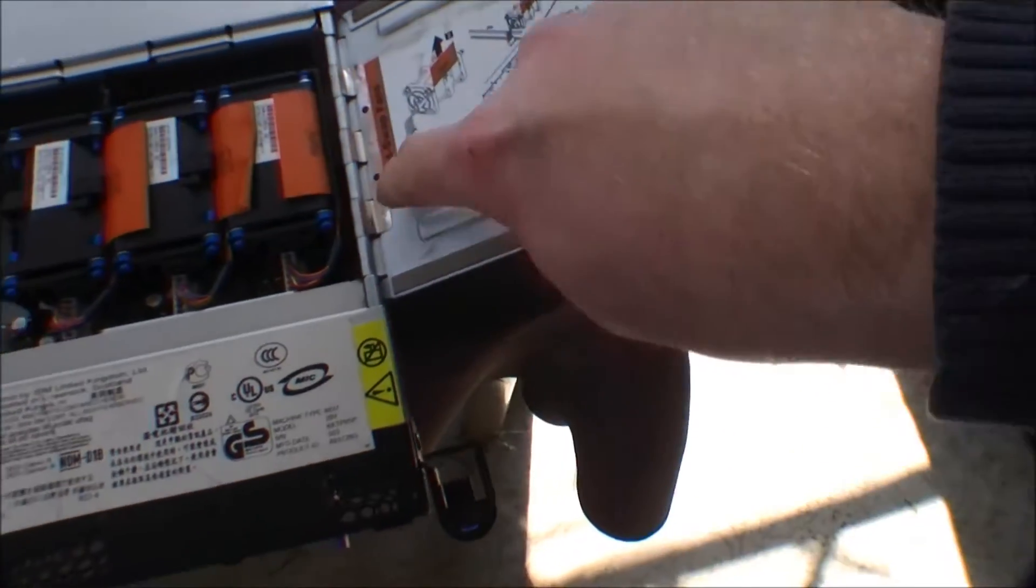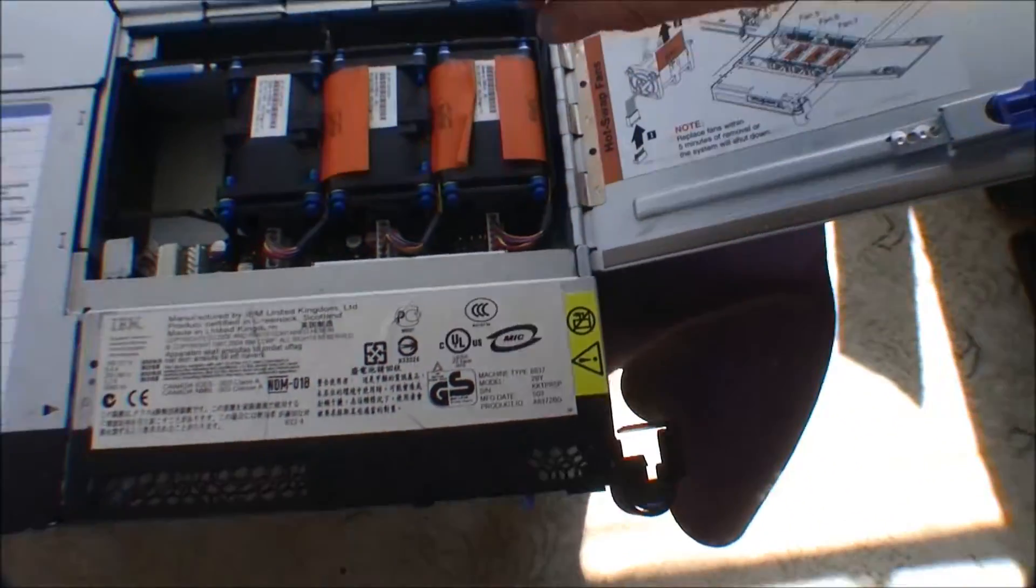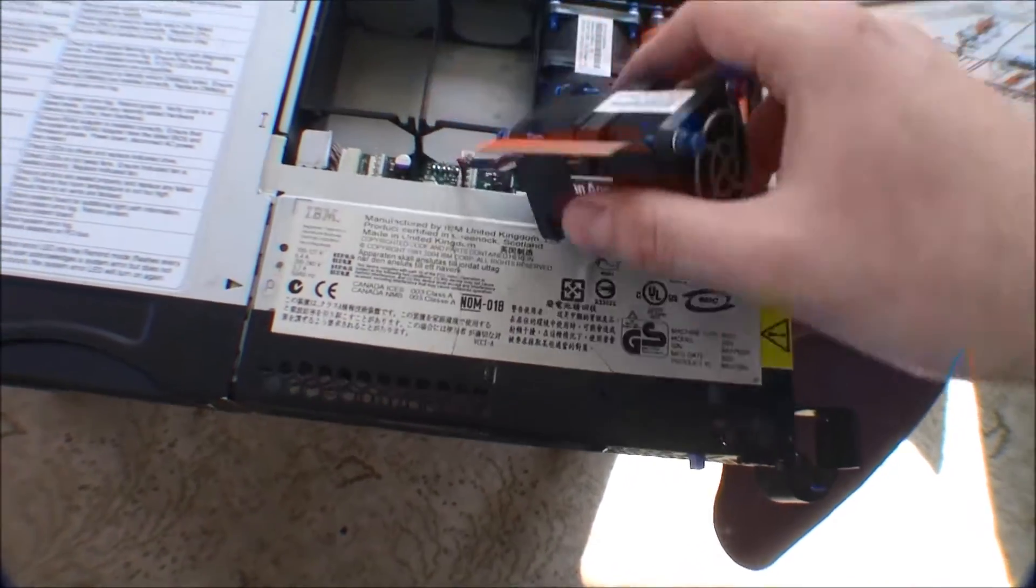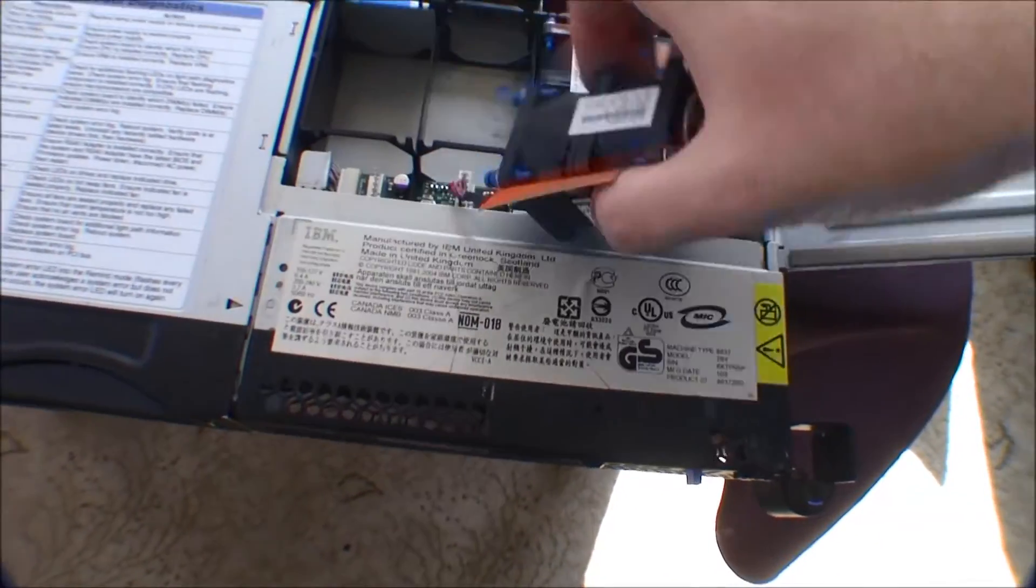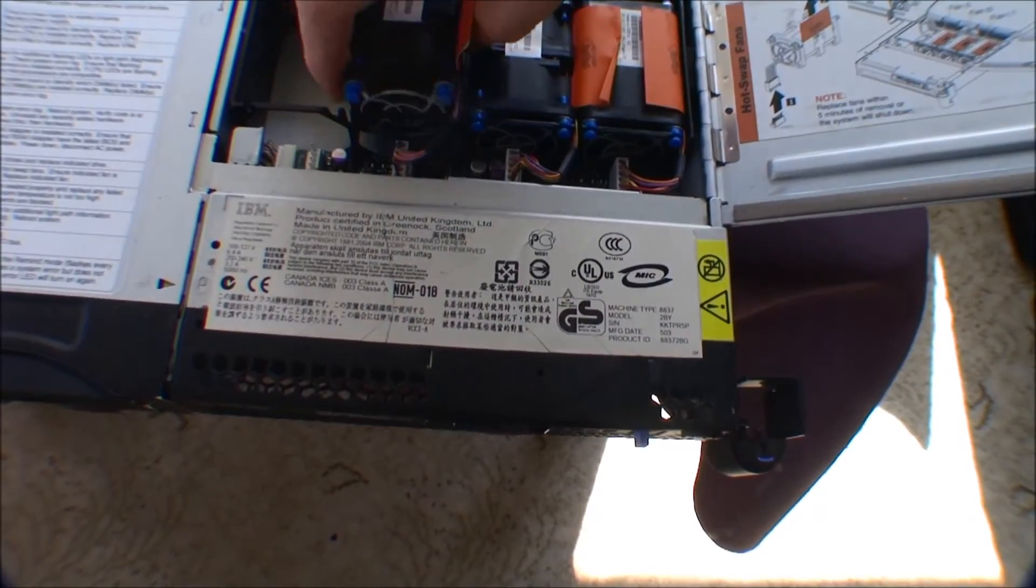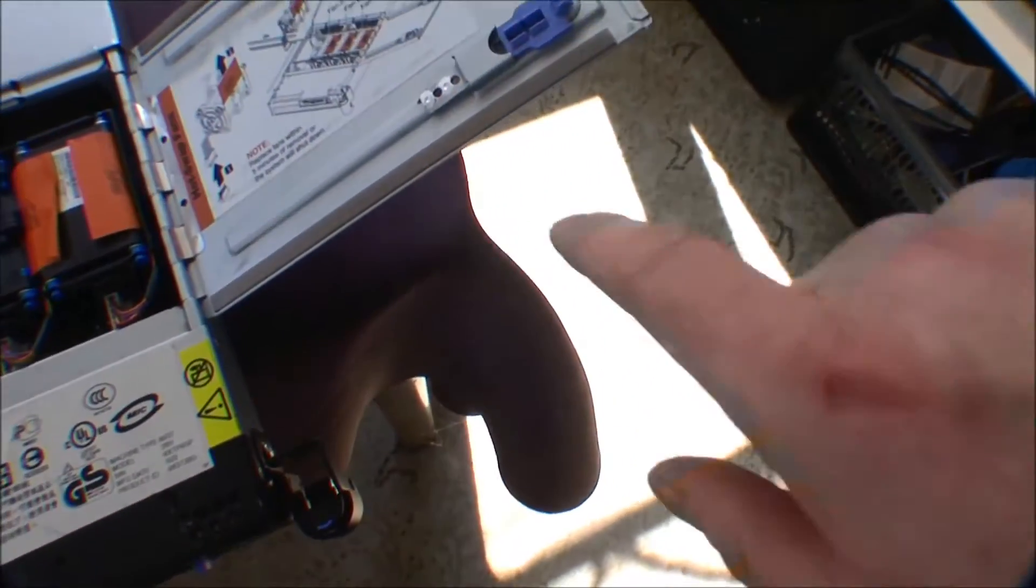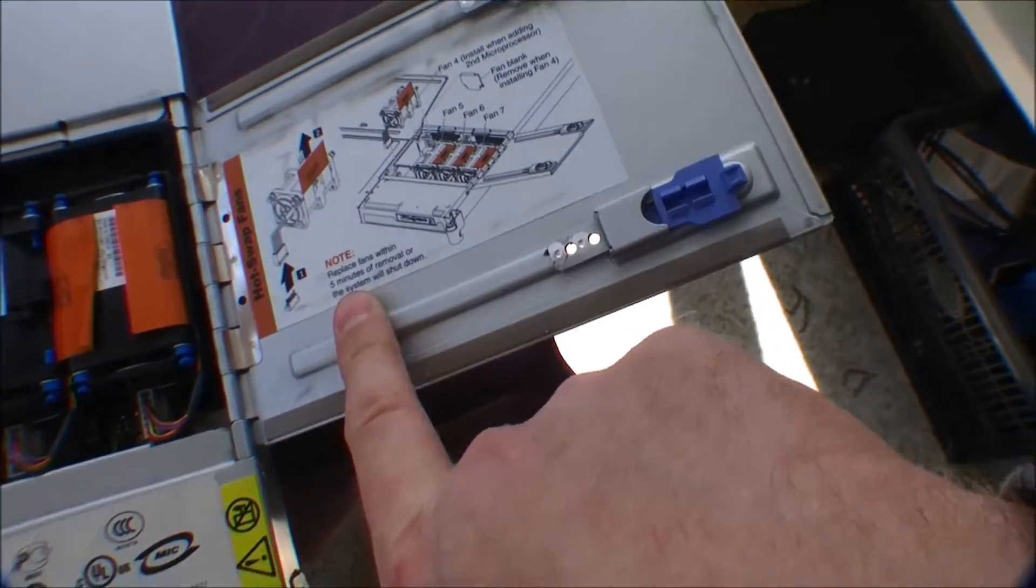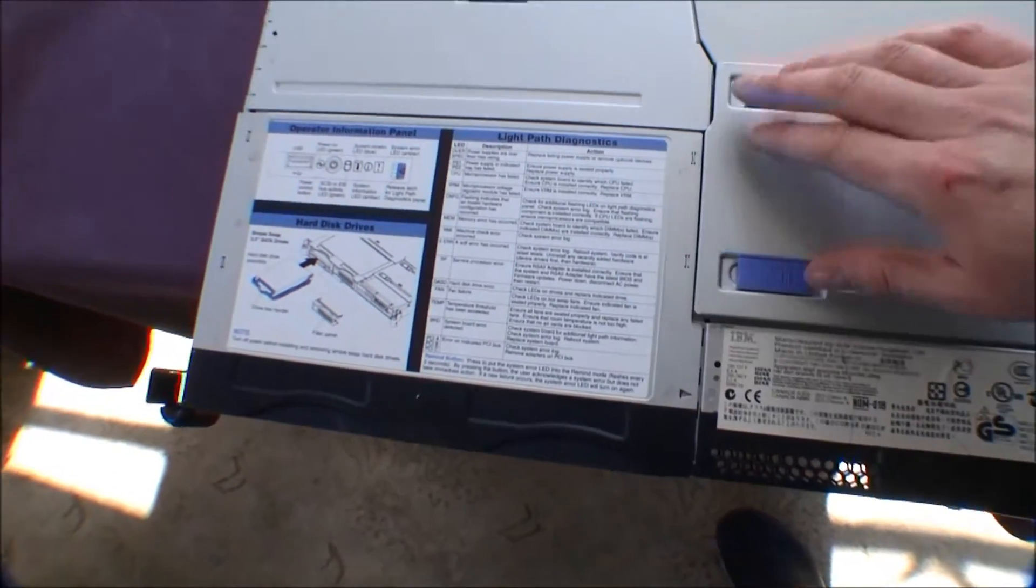And everything with orange is hot pluggable, so these fan blowers can actually be unplugged while the server is running. Just unplug this and take out the cable. And it says that you have to do this within five minutes. Otherwise, the system will shut down. Something to remember.